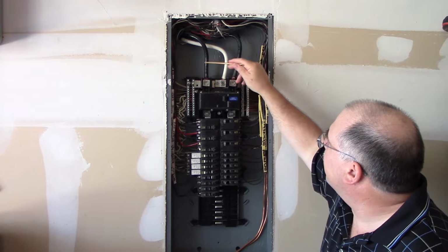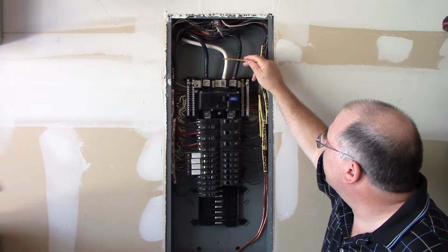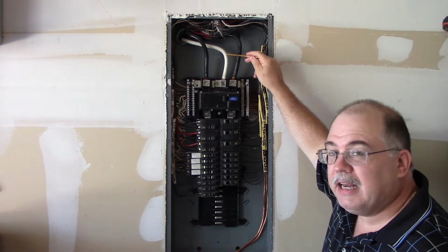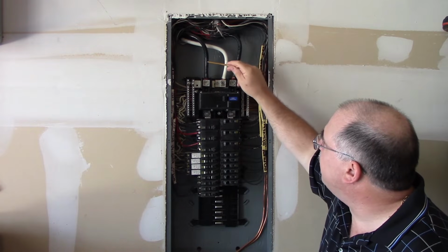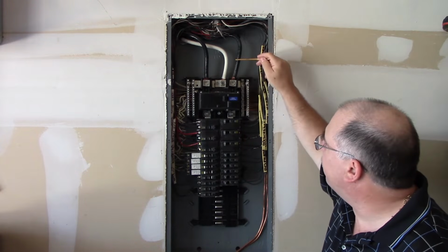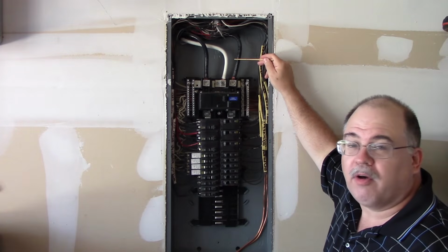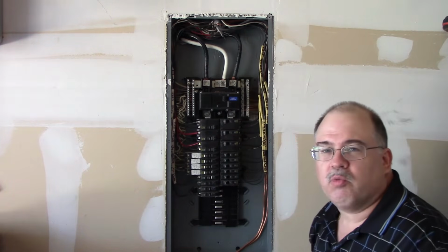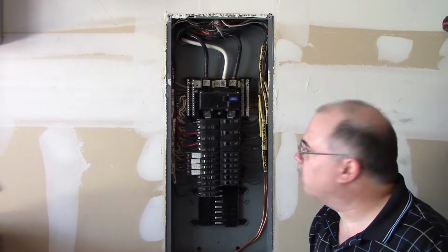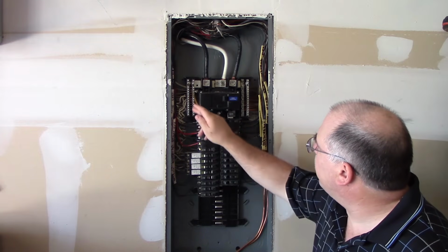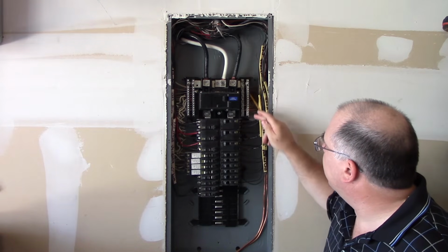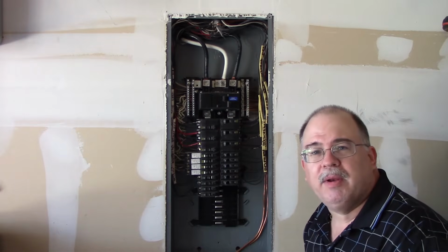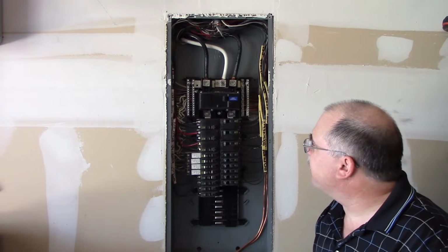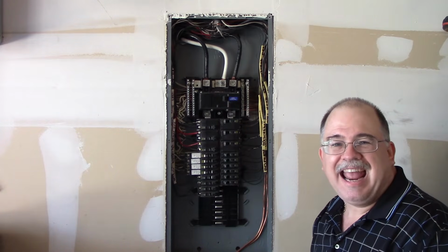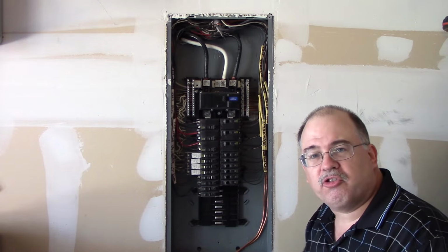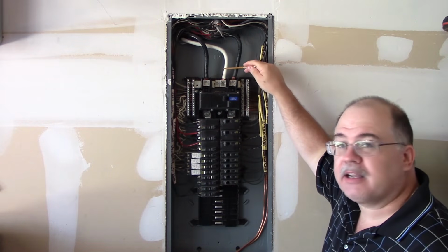And so we have an ungrounded conductor, and we have what's called a grounded conductor. In this case, it's neutral. And it is neutral because it is neutral to each one of these legs. So from here to here is 240 volts. From here to here, it is 120 volts. And those, of course, are nominal voltages. Now this bus here, as it comes across here and down here, this is all one common bar or bus that connects the grounded conductors and the equipment grounding conductors together with the grounded conductor.